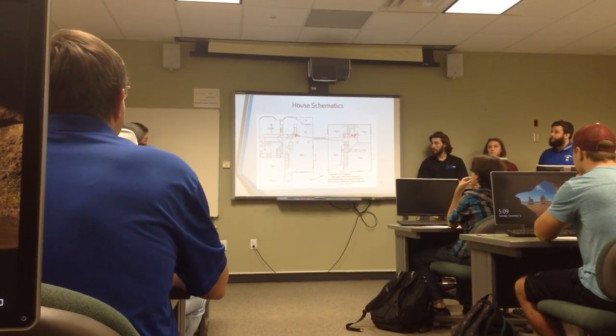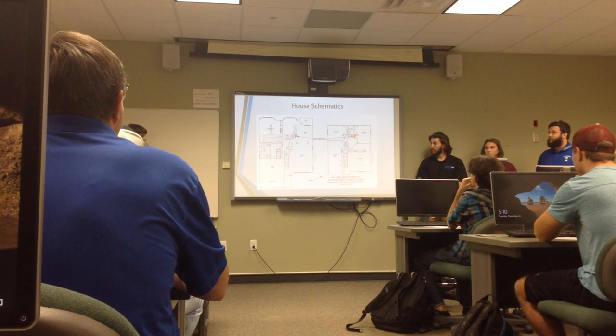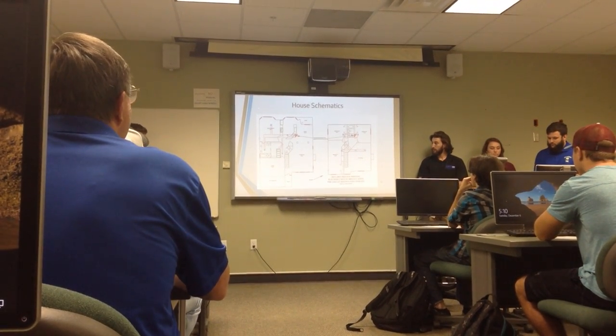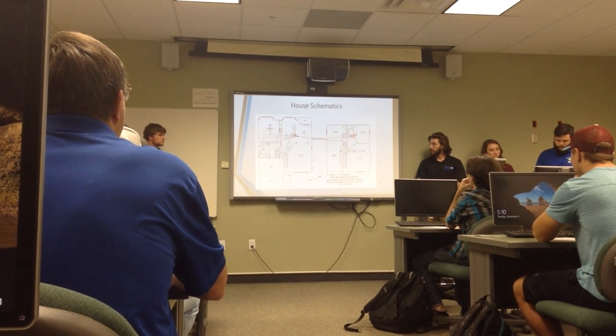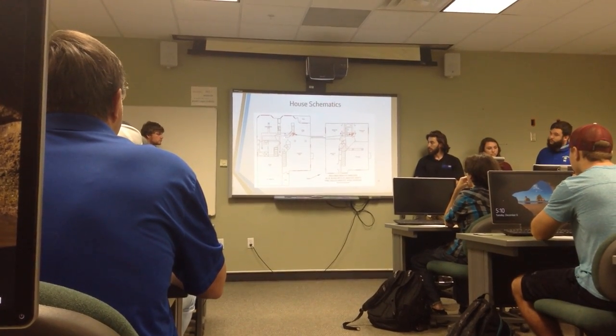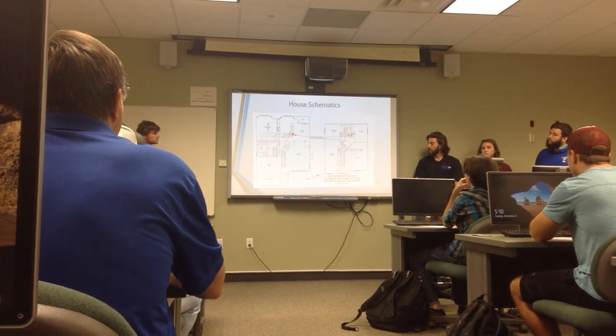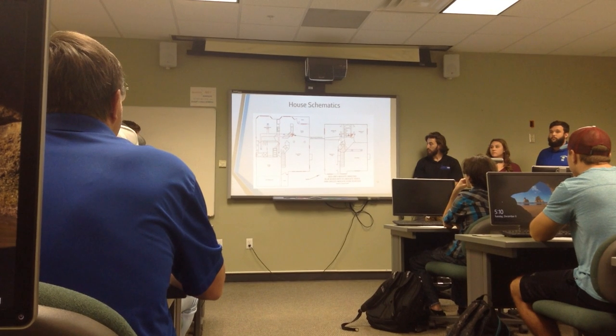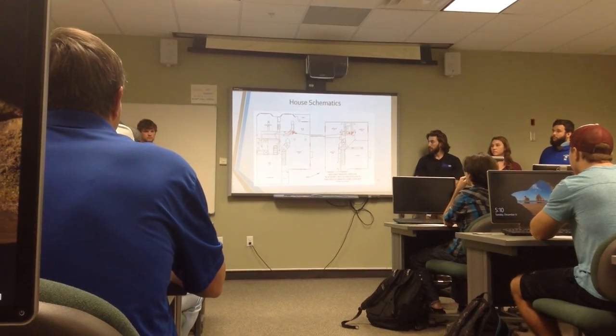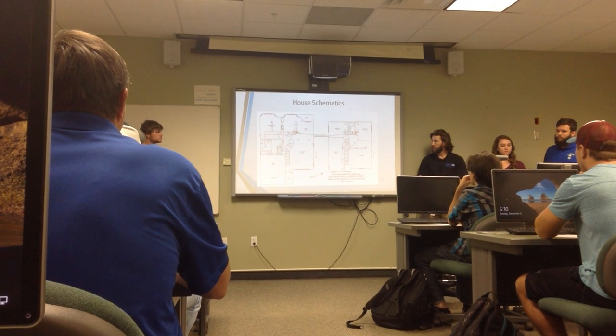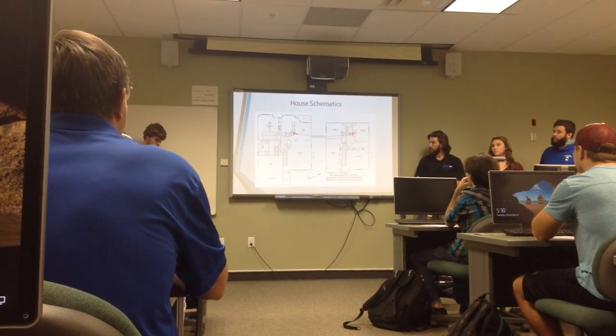This is the schematic of the house we analyzed. As you can see, there's the garage, front door, living room going into the dining area, kitchen, master bedroom, walk-in closet, and bathroom. On these CAD drawings, we've indicated where every window is, with dark red lines around the edges for the first and second floor. We've also indicated where the ducts are with blue dashed lines, and where the trunk lines for the ductwork are. The air handler sits upstairs in a closet. The thermostat is right next to the air handler. The circles indicate where we placed each HOBO sensor — one outside, one by the sink and dishwasher, one on the south-facing wall downstairs, one upstairs, and one right next to the thermostat.